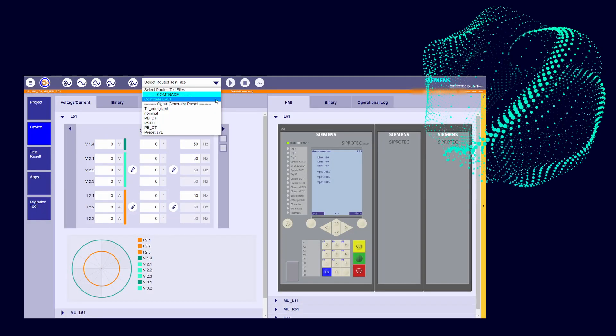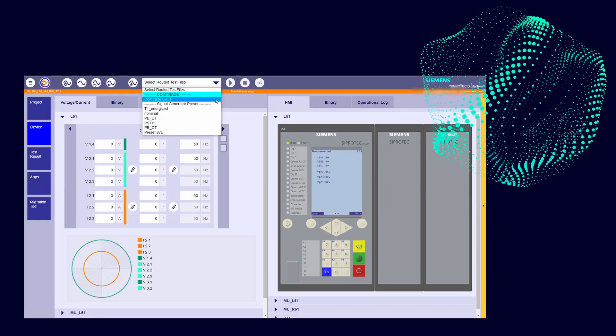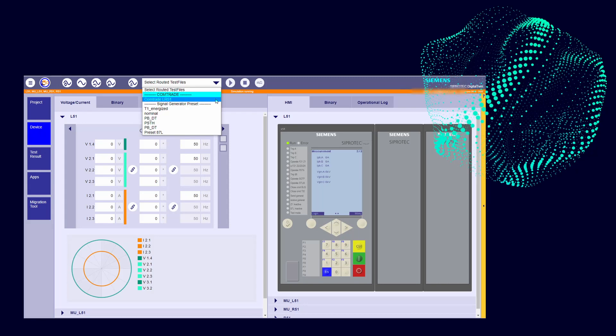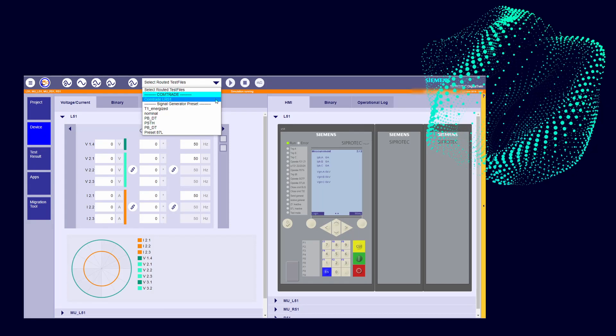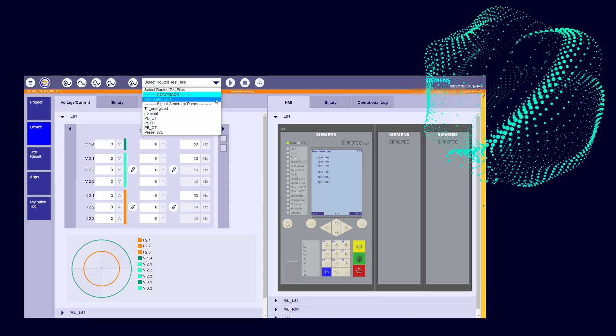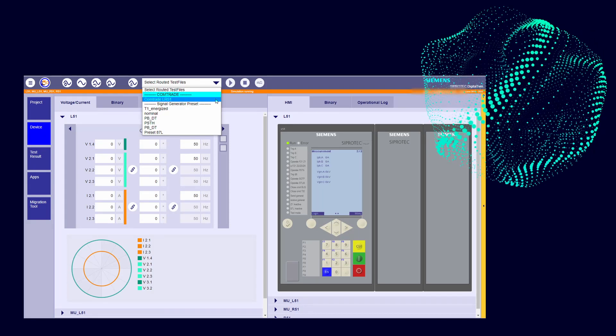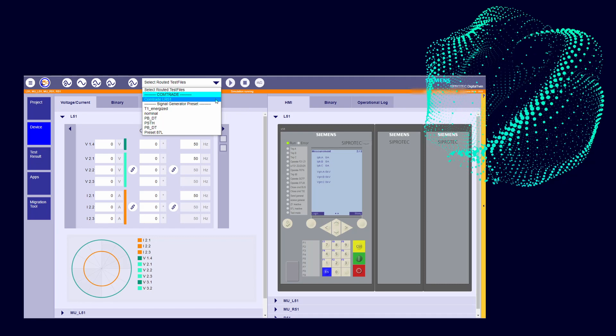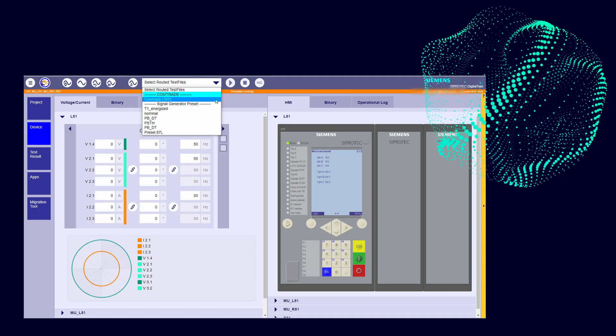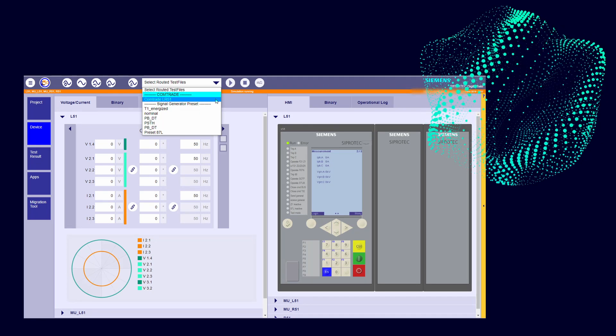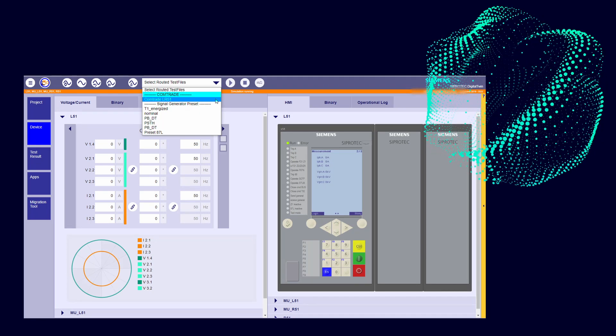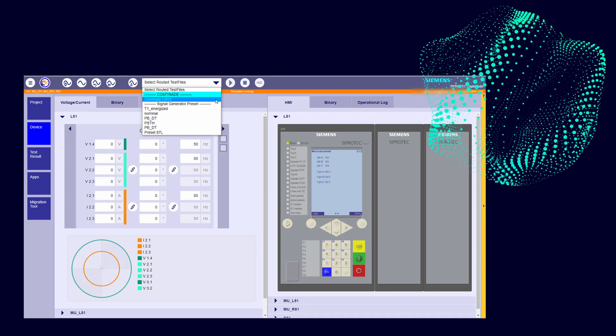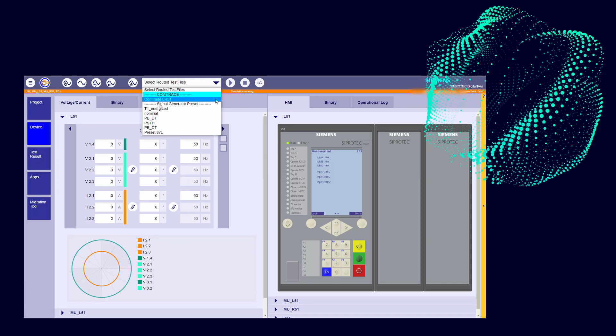The first thing that we need to think about when we test a Line Differential Protection is that we need to inject both ends of the line simultaneously. And the best way to do it is using the COMTRADE replay. So we will use one file, including the injection for both ends.